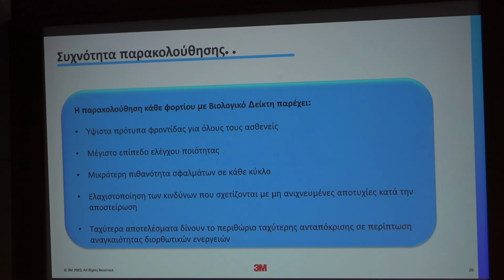But in general, when the approach is every load monitoring, for sure it will provide the highest care of the patient and also the highest quality level for the staff. And again, the most important part, it will reduce the risk of undetected failures, because we are trying to monitor something we cannot see in a closed autoclave, the door is closed, and at the same time we are killing microorganisms that we don't see. Therefore, not only the physical parameters, but we need more data about the assurance levels. And today, we mentioned that there are fast systems, so if needed, these fast systems will provide you time in order to take corrective actions.